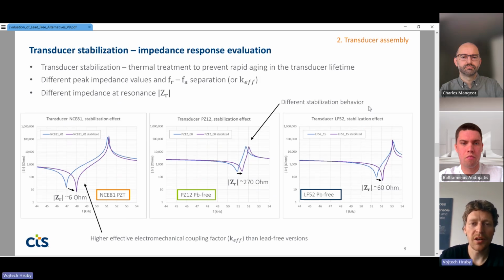After we preloaded the transducer, we did a stabilization procedure, which is basically thermal treatment. This is done to prevent rapid aging of the transducer over its lifetime. You can see that the difference between resonance and anti-resonance frequency, which corresponds to the effective electromechanical coupling coefficient, is much higher for the PZT transducer and lower for the lead-free alternatives. Also, the final impedance magnitude at resonance is really different among these three transducers: it is 6 ohms for the PZT transducer, then 270 ohms for the PZ12 lead-free, and 60 ohms for the LF52 lead-free transducer.